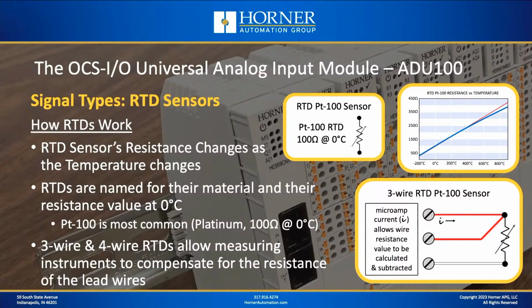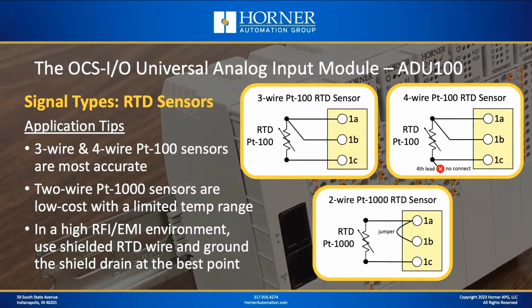So any quality RTD measuring instrument, like the ADU100, will have the ability to work with 3-wire and 4-wire RTDs. What the ADU100 does is send out a small microamp current, and it can use that current to measure and calculate the lead resistance of the wire, and subtract that out to ensure that the temperature reading that's reported is strictly the temperature at the probe. So that's critically important with PT100 RTDs. Now, when it comes to wiring the RTDs, they use the A, the B, and the C terminal. And I mentioned just a minute ago that you have 3-wire and 4-wire RTDs available. They're wired identically, except with the 4-wire RTD, you simply tie off that 4th lead. Now, there are some very high-end, generally scientific measuring instruments that will take advantage of that 4th lead fully, but you don't find those very commonly in industry.